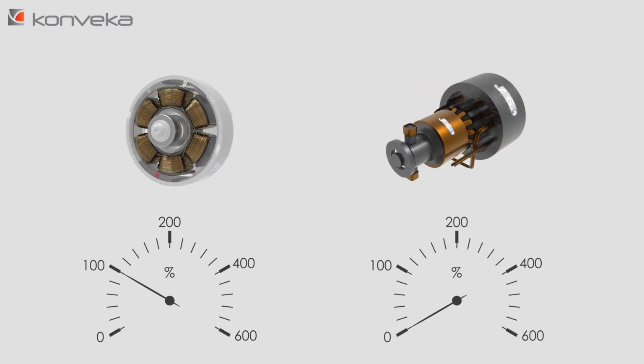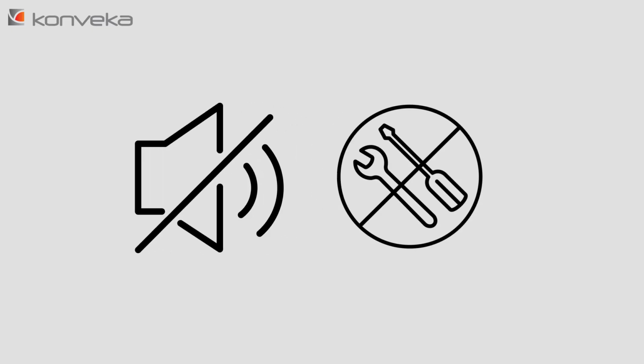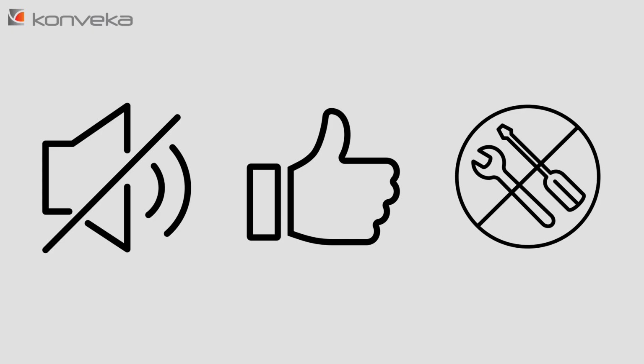The EC motor starting current is equal to the operating current, so its operation is smooth and overloads are prevented. The AC motor starting current is up to 6 times higher than the operating current. Such overloads reduce the service life of the fans, the control system, and the entire power installation. The EC motor is a low-noise motor with a noise level that is considerably lower. It has no brushes that require permanent replacement, resulting in low maintenance and an extended durability.